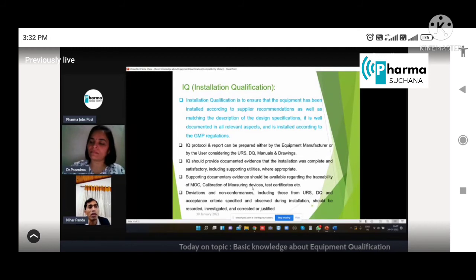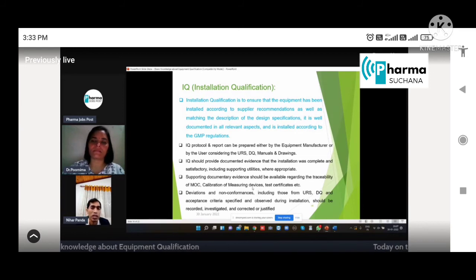Then supporting document evidence should be available regarding the traceability of MOC, material of construction. Supporting documents, certificates should be there. The equipment manufacturer should provide the certificates related to MOC, and calibration of measuring devices. If the equipment has any measuring devices like ampere meter, pressure gauges, Magnehelic gauges, those should be calibrated before installation, and those calibration certificates are to be provided by the manufacturer. If they are not providing, then those devices should be calibrated at the user site before usage.